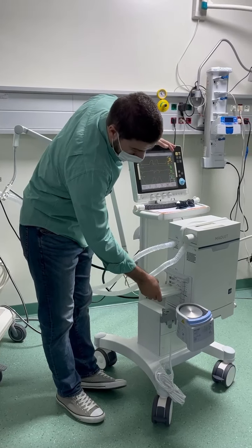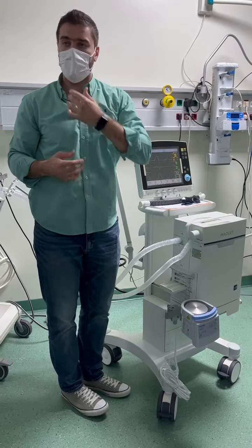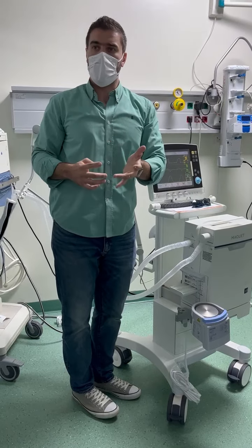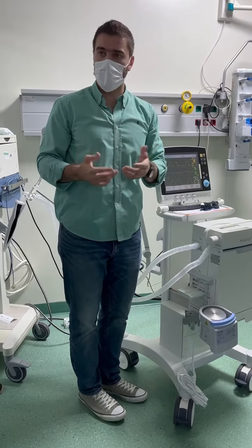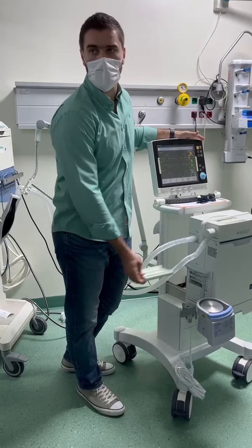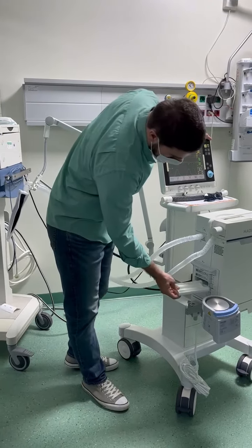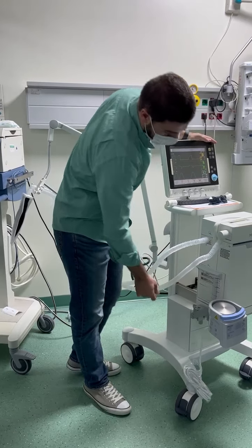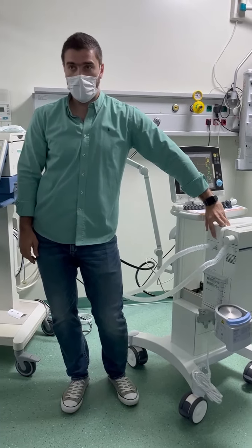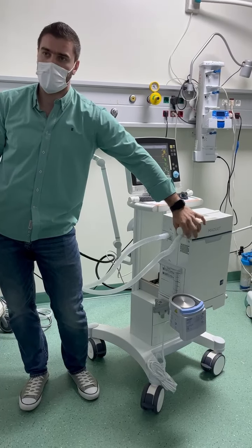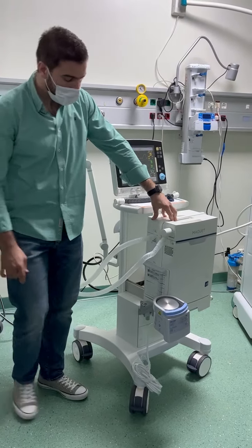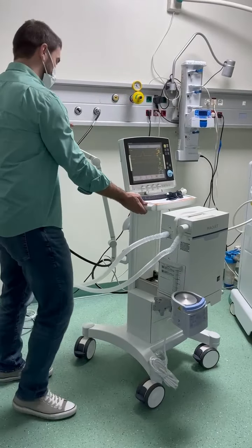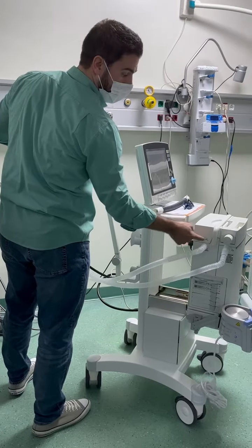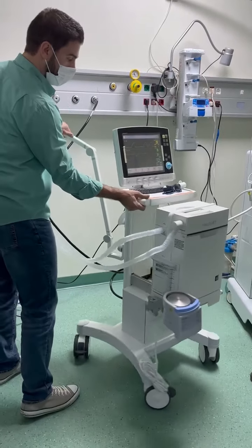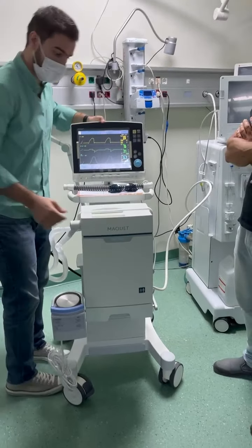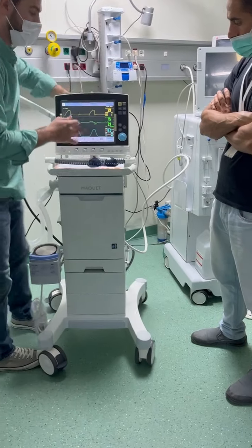Okay. Also, in the future, if you need to upgrade the ventilator to bring a CO2 module, Y sensor module, or any extra modules, you just take this one and bring the module and plug it in. It's only plug and play. Okay. So this is the side. This part is inspiratory and this is expiratory, as written here. Okay. This is a humidifier with the holder. Can you see it? The inspiratory and expiratory. Okay. Right. This is the screen. We finished the base unit.